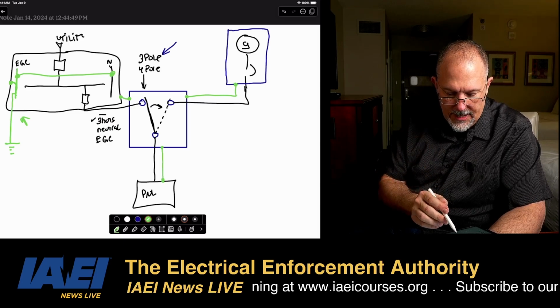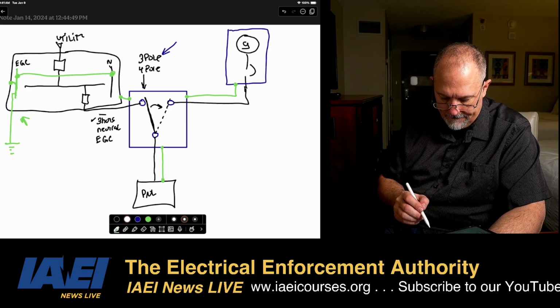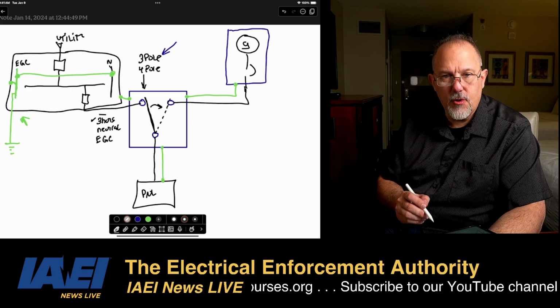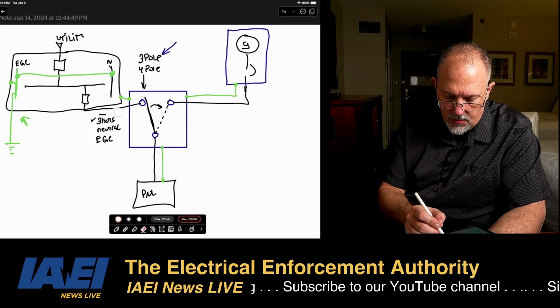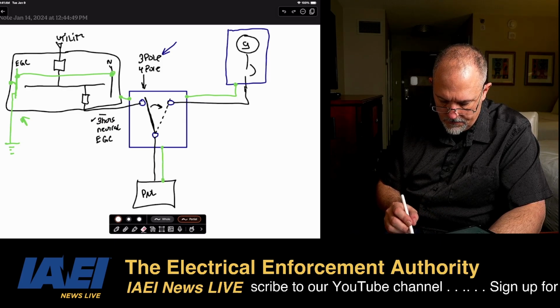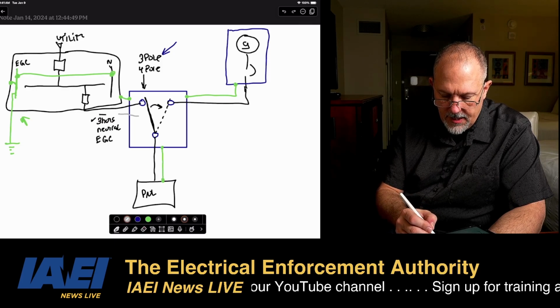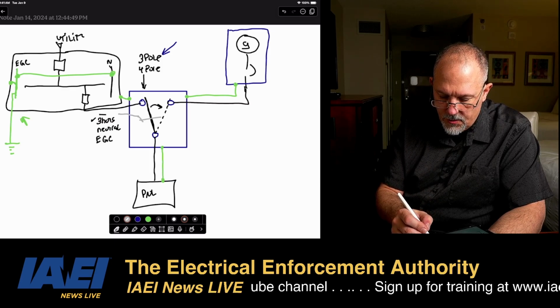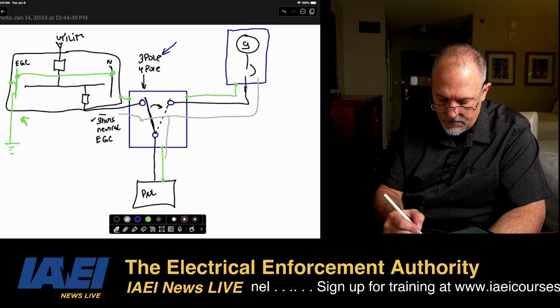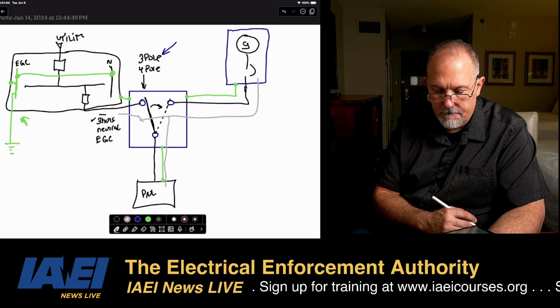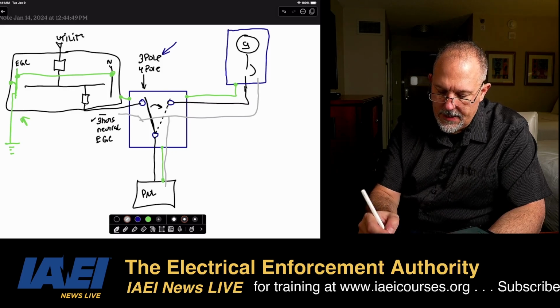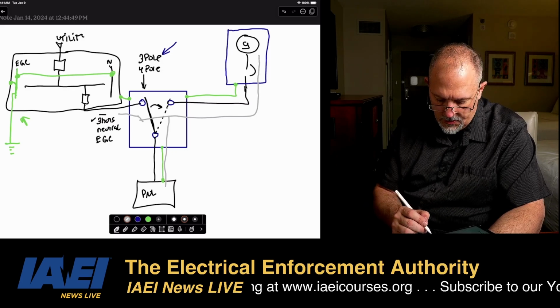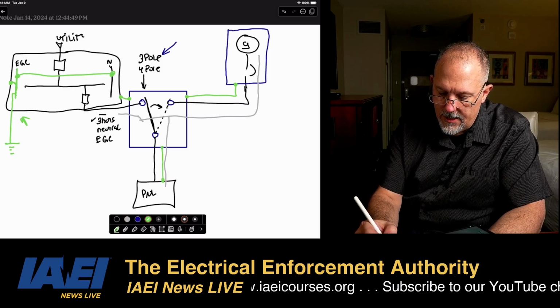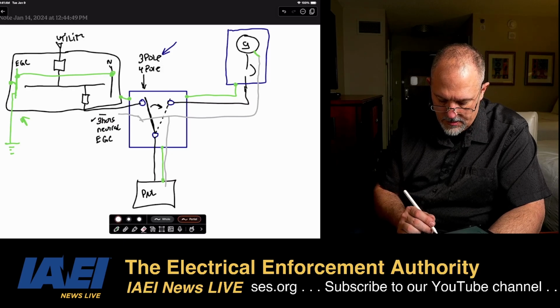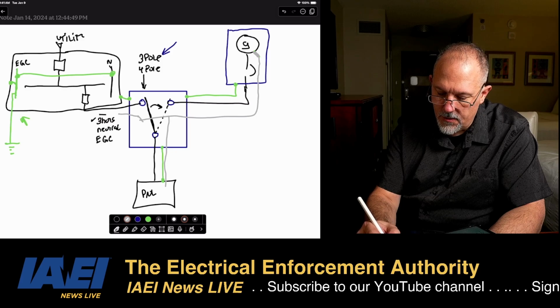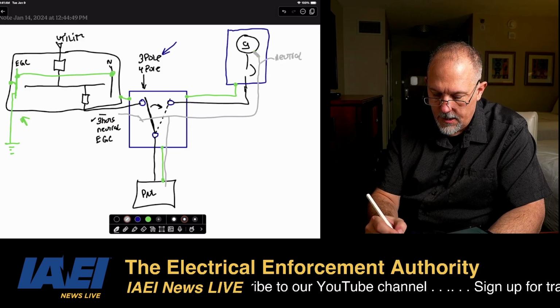And my neutral, now what happens to my neutral? Let's pick a color for neutral. How about gray? Will gray show up? Let's try it. If I have my neutral coming in and I'm not switching it, then my neutral just basically passes through and passes down to this equipment with my hot. Right? And then up here, I'll have a neutral point. I'll also have a ground. So this is my ground. I make sure that my neutral, so this is neutral, and this is ground.